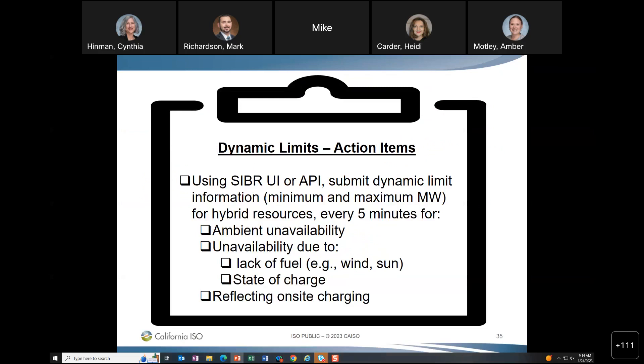As a scheduling coordinator, you need to submit dynamic limits using the SIBR UI or the API — minimum and maximum for every five-minute interval. There are four scenarios where you would want to do this: ambient unavailability, unavailability due to lack of fuel or state of charge, reflecting on-site charging, or other output limitations. You would reflect these actual operating constraints in your dynamic limits.